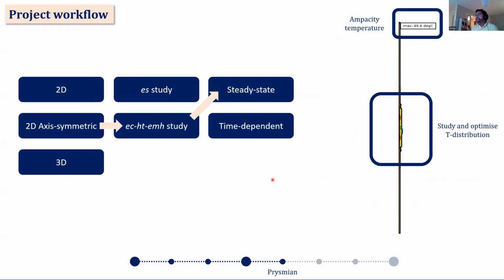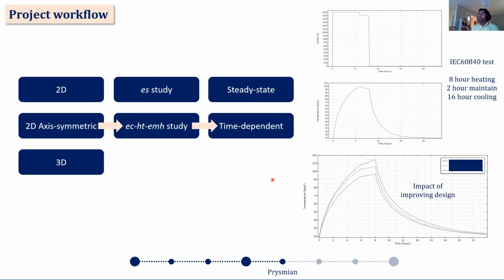This was first done at steady state, then I made improvements to better allow heat to dissipate. Finally, with a time-dependent study, we simulated the IEC 60840 test, which runs over 24 hours - the first 8 hours involve heating it to about 5 to 10 degrees above the design capability.